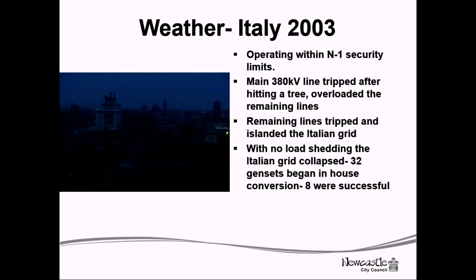As a result of that, technically it could have withstood it for 15 minutes. It withstood it for 24, then that collapsed. And once that happened, the power spread around the remaining lower voltage lines that fed into Italy, and they all began to trip. Italy then became a power island, but because it was importing power in the first place, it did not have enough generation to support its load. And as a result, it went black.